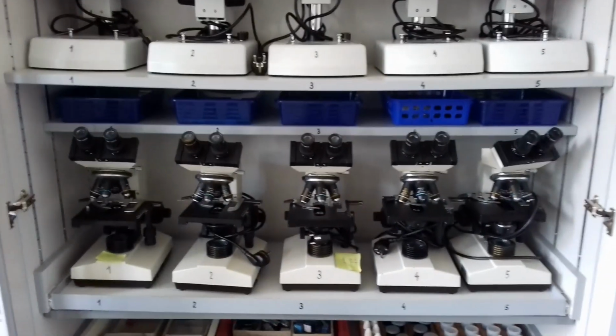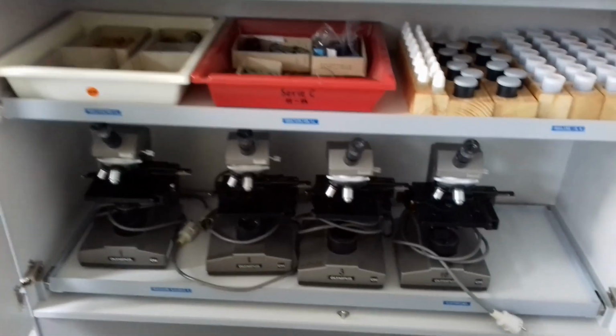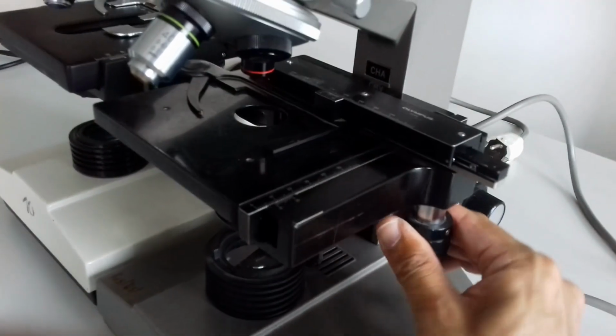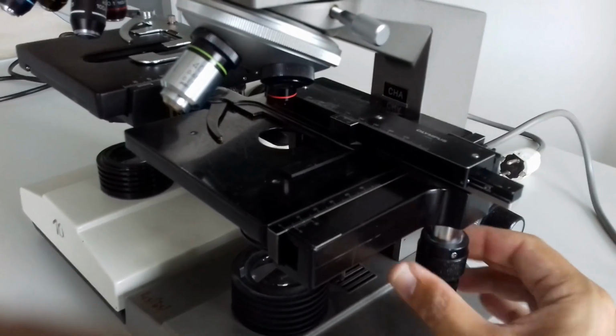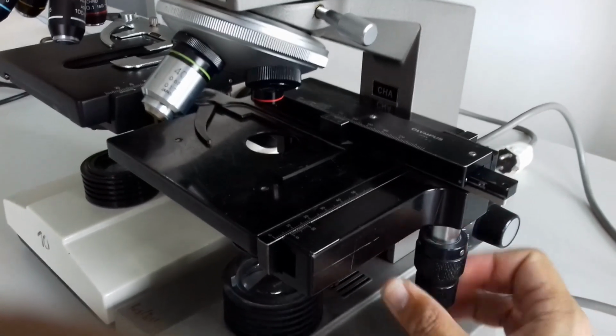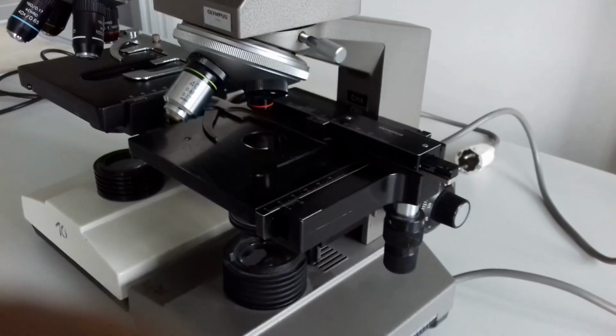Okay, so first of all, I want to give you some background information. In the school where I work, we've been using Olympus CHA quality microscopes for around 30 years. So they've been in operation for a very long time and they worked very reliably. However, in recent years, the gearing of the microscope started to become difficult to turn, and the reason is that the lubrication oil started to become solid. This is a normal thing that happens. You refer to this as gumming up of the oil, and when that happens, you simply send your microscope to the microscope company, to a service company, and they will take the microscope apart. They will remove the old oil and re-lubricate everything, and then you're fine again, and the microscope works.